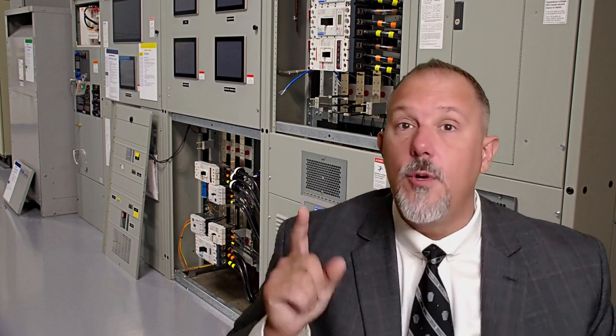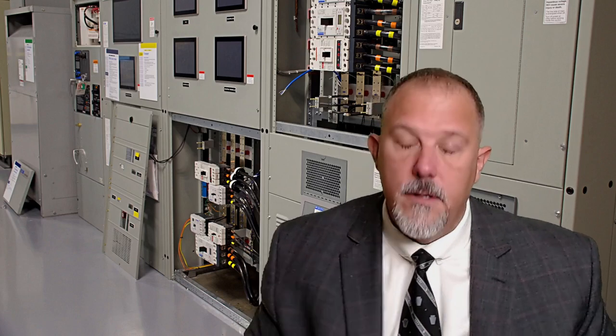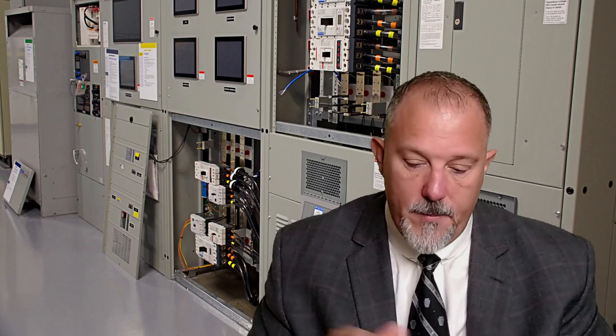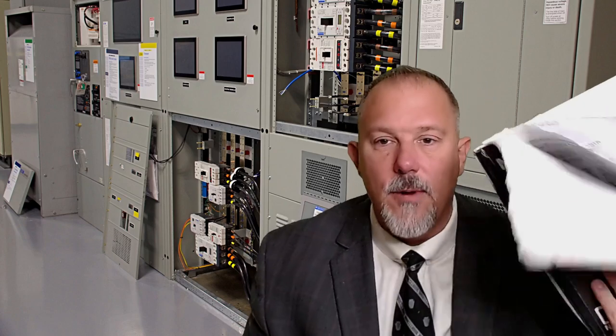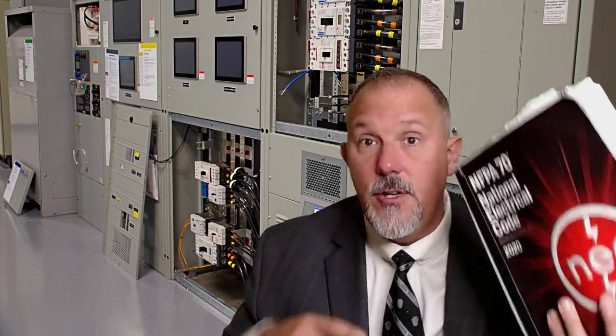So, proper application of the products. People ask me, what about the National Electrical Code? What's the relationship between the National Electrical Code and 70E? Well, if you would have installed that product correctly, you would not have had an available fault current greater than the short circuit current rating of that equipment. And that is a 110.10 requirement in the National Electrical Code. And in the recent changes in the NEC, we saw many changes throughout the National Electrical Code raising the awareness of these ratings.